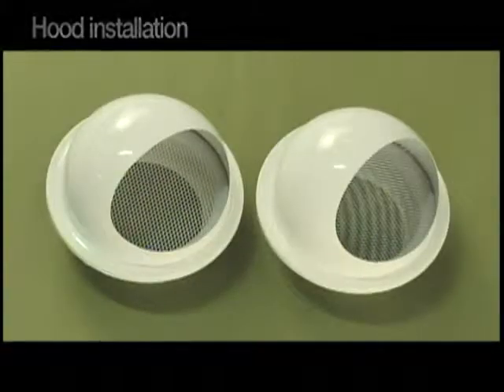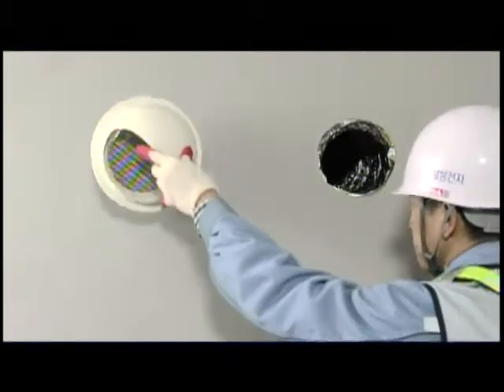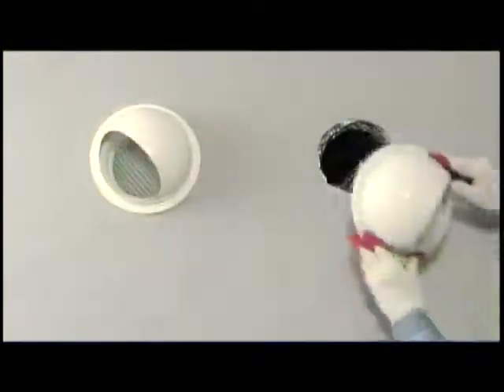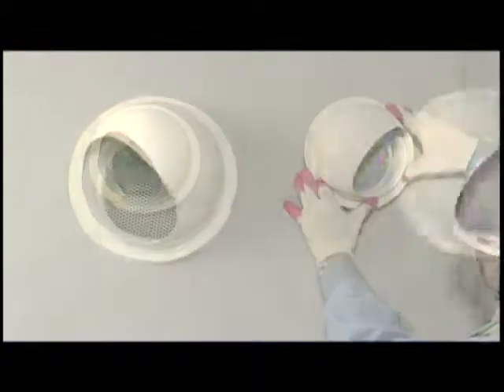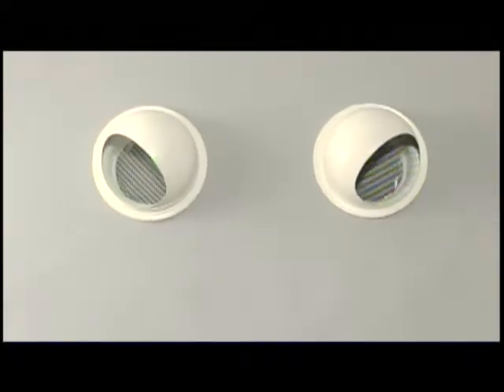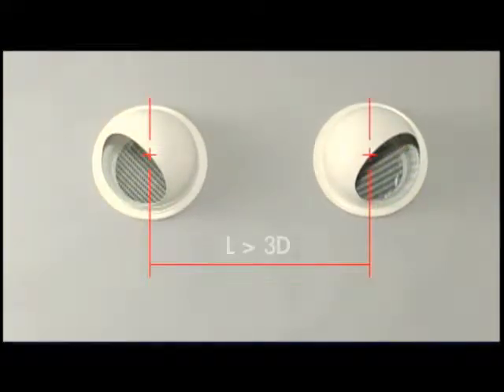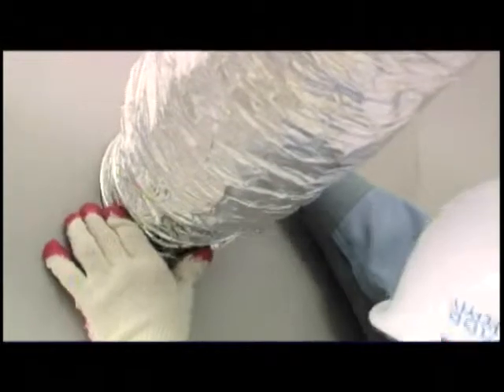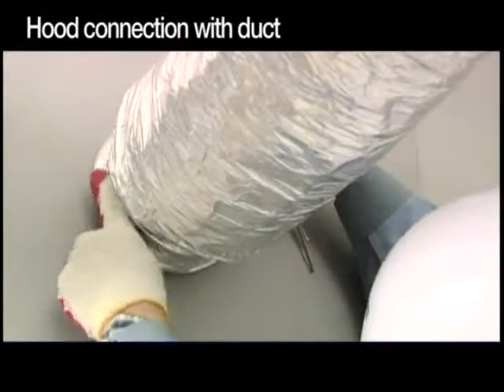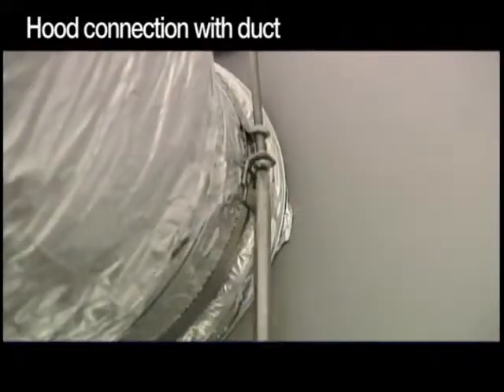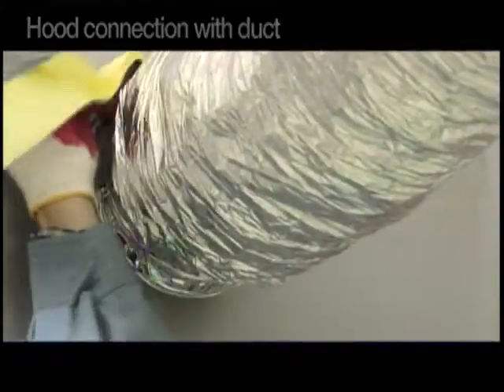A hood is installed so that the duct can be connected to the outside. The inlet and outlet ducts should be separated sufficiently so that the discharged air does not re-enter the inlet duct. This is called a short circuit effect. When connecting the duct to the hood, first fix them with a clamp and wrap the joint with the aluminum tape to prevent air leakage.